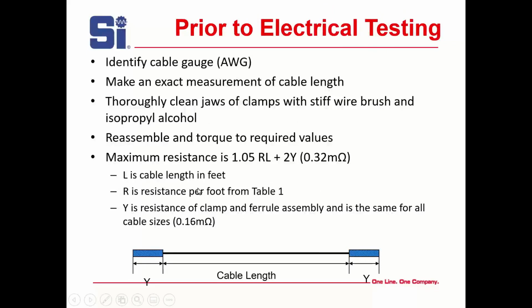So prior to electrical testing, you want to identify the cable gauge and make an exact measurement of the cable length. And I've got a diagram there to help you out. Thoroughly clean the clamp with a stiff wire brush and isopropyl. I don't even clean my feet that well. Reassemble and torque to required values.